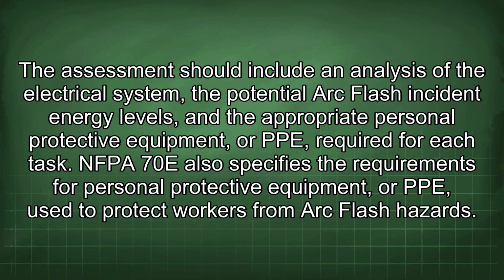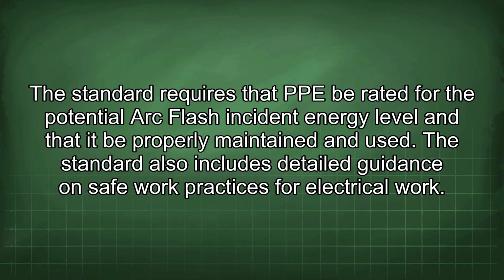NFPA 70E also specifies the requirements for personal protective equipment used to protect workers from arc flash hazards. The standard requires that PPE be rated for the potential arc flash incident energy level and that it be properly maintained and used. It also includes detailed guidance on safe work practices for electrical work.